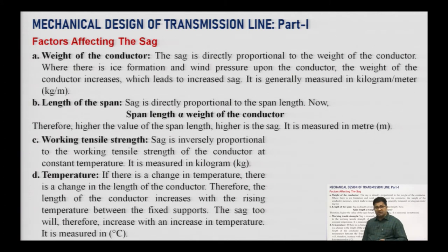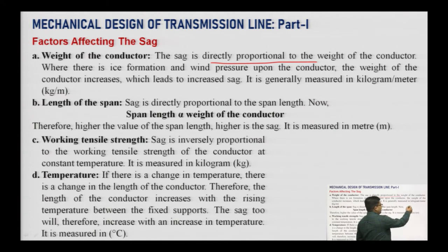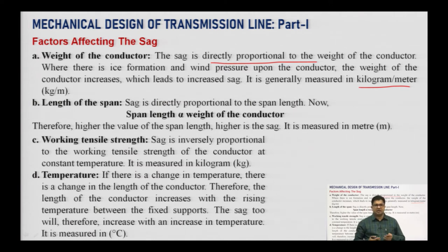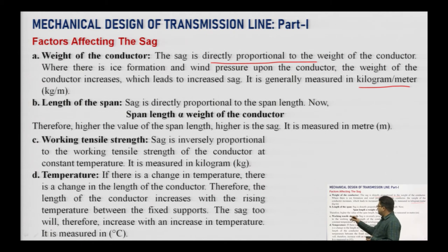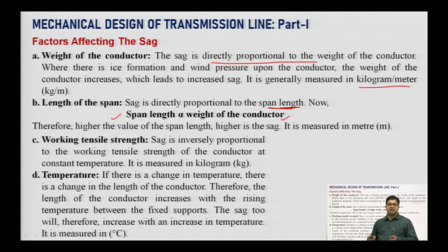In more detail: the sag is directly proportional to the weight of the conductor, which is measured in kilograms per meter — increasing conductor weight increases sag. The sag is also directly proportional to span length. The span length is proportional to the weight of the conductor: if the conductor weight is large, you require a larger span length.